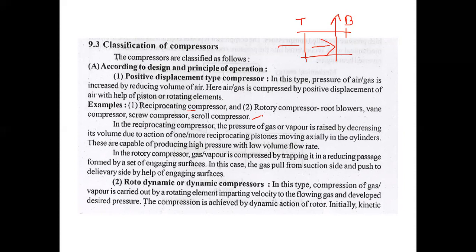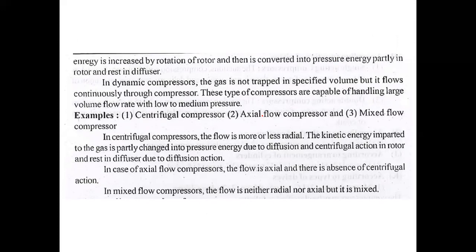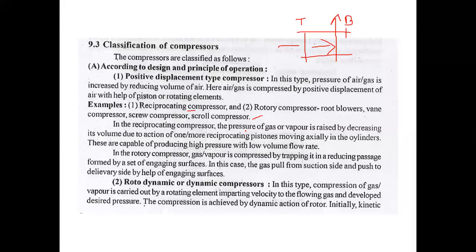The second type is the roto-dynamic or dynamic compressor. In this type of compressor, compression of gas is carried out by a rotating element that imparts velocity to the flowing gas and then develops the desired pressure. The compression is achieved by dynamic action of the rotor. Initially, kinetic energy is increased by rotation of the rotor and then converted into pressure energy, partially in the rotor and the rest in the diffuser. In dynamic compressors, the gas is not trapped in a specified volume but flows continuously through the compressor. These compressors are capable of handling large volume flow rates with low to medium pressure.